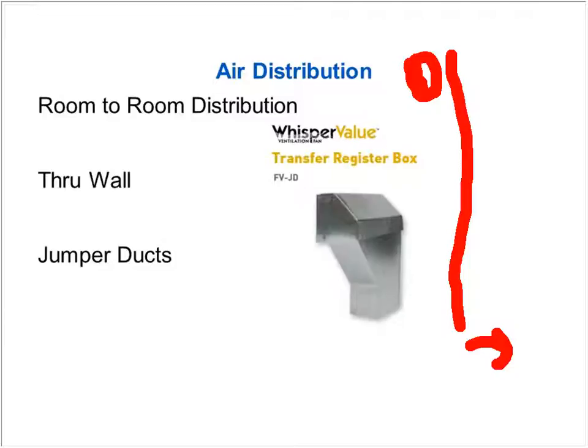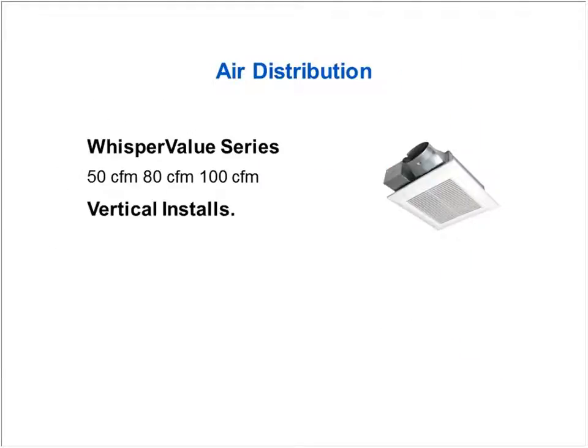And that's pretty efficient. In this case, I've got to tell you, I've seen 50, 80, and 100 CFMs, but my favorite is going to be the 50 because it's considerably quieter. You just don't get enough airflow difference between the 50, 80, and the 100. The 100 CFM tends to make way too much noise. So for example, at 50, you won't hear that over your TV. At 100 CFM, you will hear that over the TV.